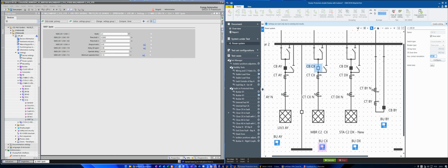When I energize the remote terminal, I have a current that will flow to these CTs. And probably I have a protection in the remote terminal line, a switch onto fault, that will operate and clear this fault. But if my bus bar protection did not see the status of the circuit breaker to put in or not put in the current, what will happen? The circuit breaker is open, but my bus bar protection is not seeing the status of the circuit breaker.